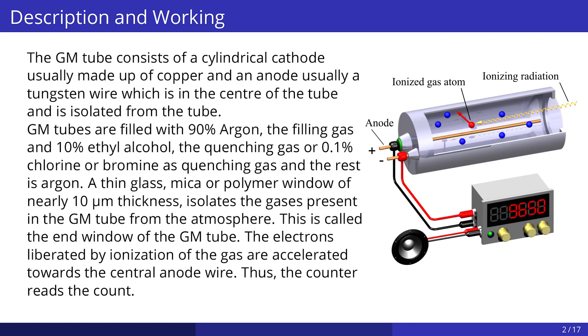The GM tube consists of a cylindrical cathode, usually made of copper, and an anode, usually a tungsten wire, which is in the center of the tube and is isolated from the tube. GM tubes are filled with 90% argon as the filling gas and 10% ethyl alcohol as the quenching gas, or 0.1% chlorine or bromine as quenching gas with the rest being argon. A thin glass, mica, or polymer window of nearly 10 micrometer thickness isolates the gases present in the GM tube from the atmosphere — this is called the end window of the tube.